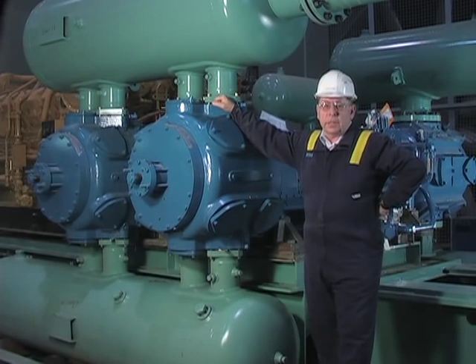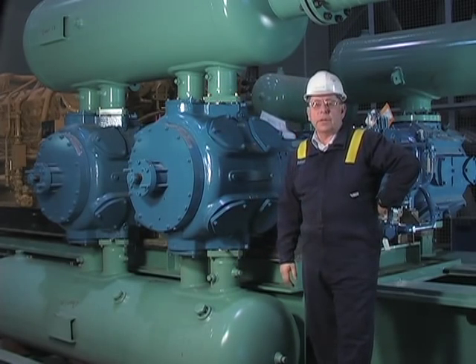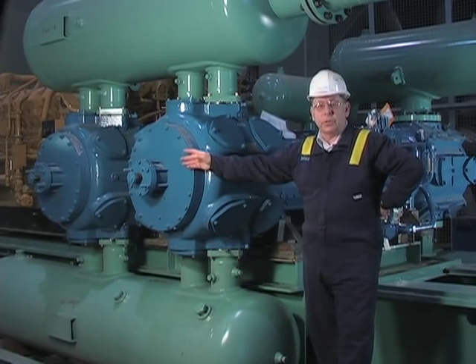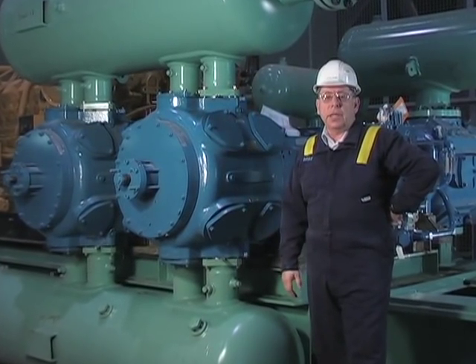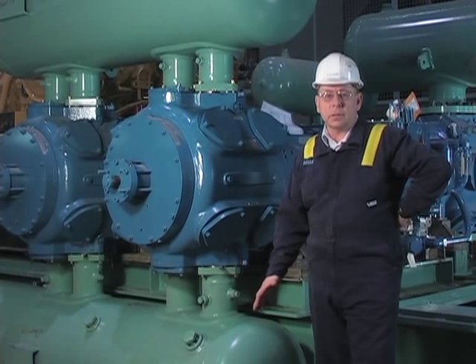Pulsations exist in the suction and the discharge systems. They travel through the bottles, the piping, off to the cooler, and then through the off-skid piping. Each wave can be greatly amplified due to a phenomenon called acoustical resonance.